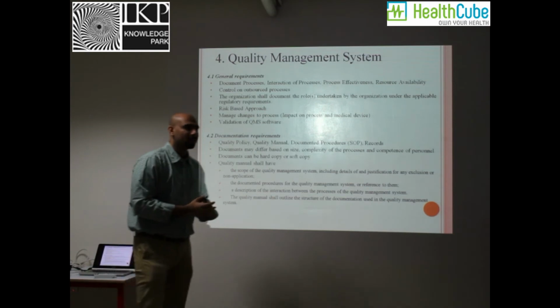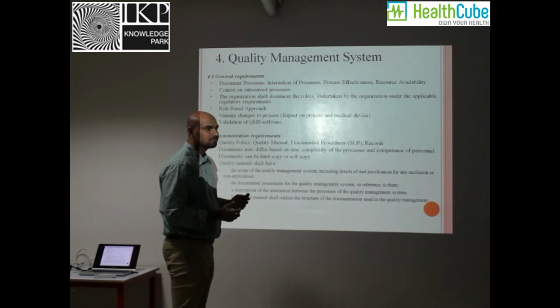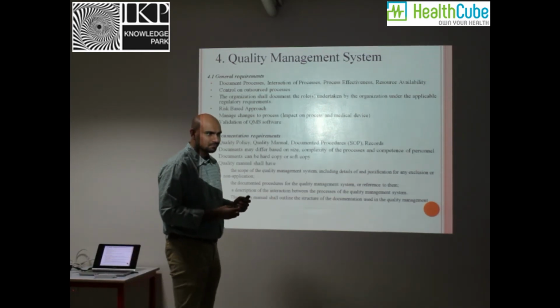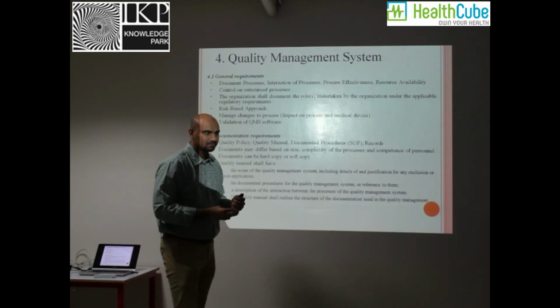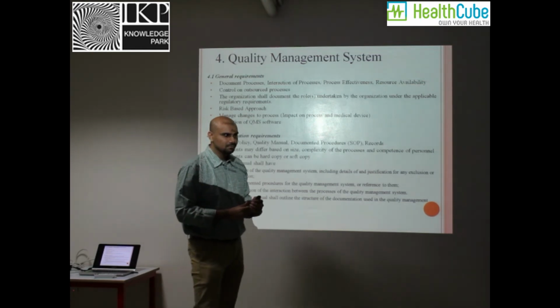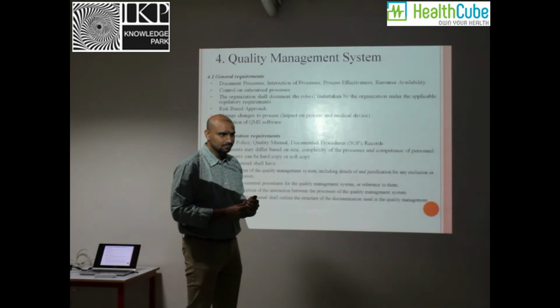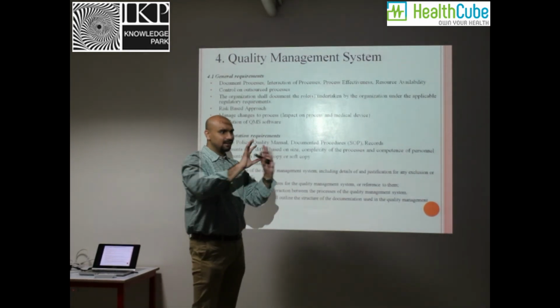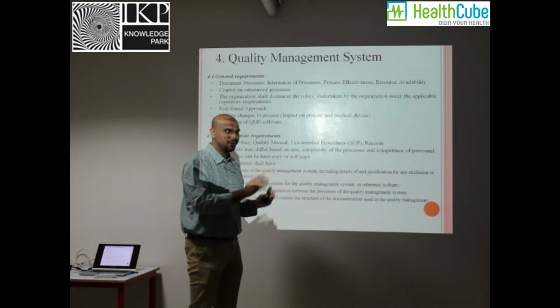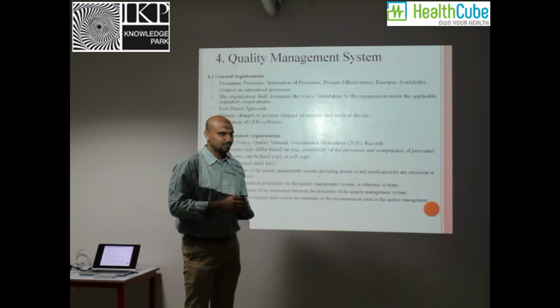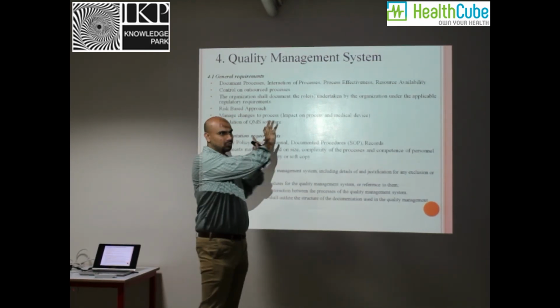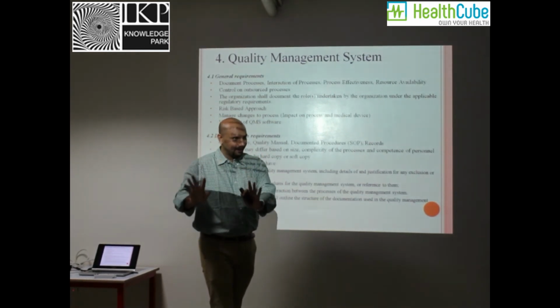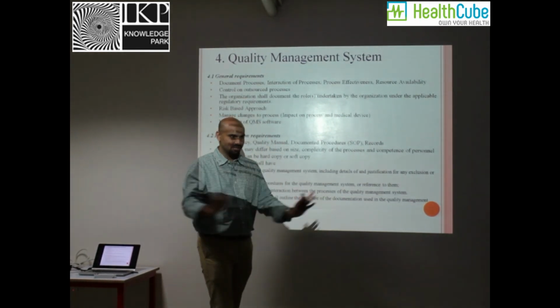In the previous page, you mentioned something about medical devices. Earlier, there was this classification of MD and IVD. It looked like some of those which fell into the IVD category, like the diagnostic devices, which are purely in vitro, were also listed as MD. Yes, that's a general description which includes medical devices as well as in vitro medical devices. Okay, so we'll be doing the in vitro part separately? No, 13485 is for medical devices and IVD also. It's in general for everything.